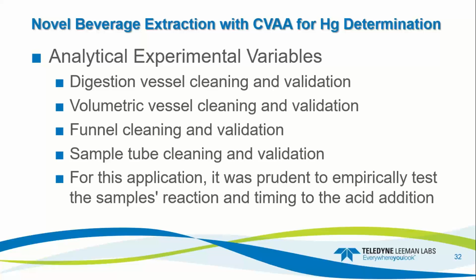So some of the analytical experimental variables within this method: digestion vessels, cleaning and validation, volumetric vessels, cleaning and validation, funnel cleaning and validation, sample tube cleaning and validation. So there's a lot of pieces to this process where contamination can be introduced into the system. So you really need to use the best GLP possible. For this application, it's prudent to empirically test the sample's reaction and timing to the acid additions.